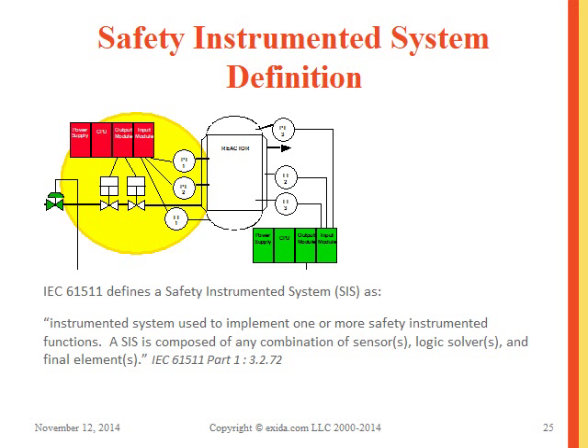IEC 61511 defines a safety instrumented system as an instrumented system used to implement one or more safety instrumented functions. A SIS is comprised of any combination of sensors, logic solvers, and final elements. There are no restrictions on the type of technology used or the size of the system. A SIS can comprise one single function, but often has anywhere from a handful to several hundred functions depending on the application.